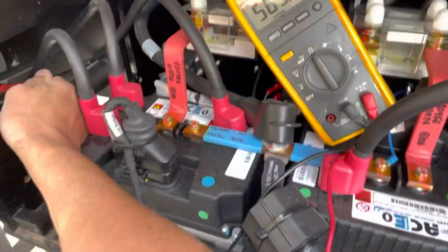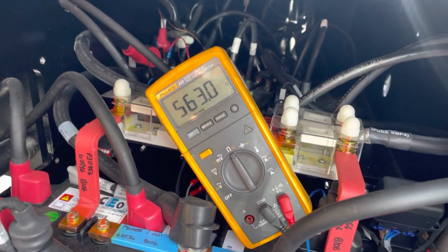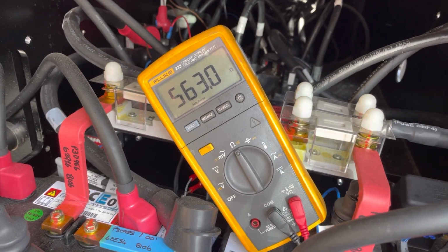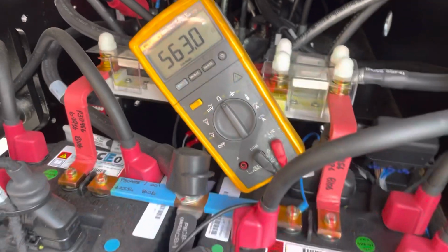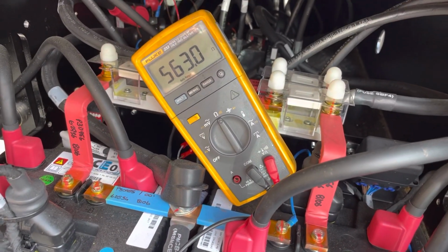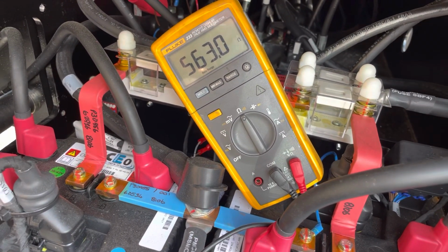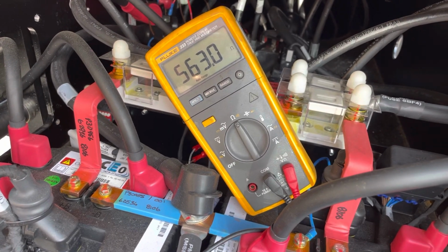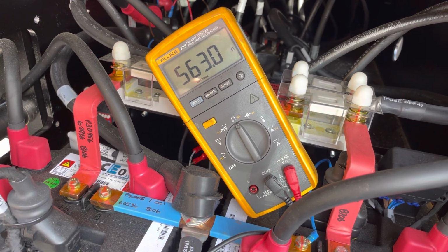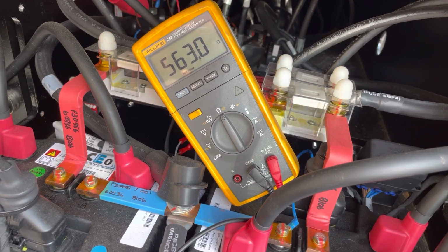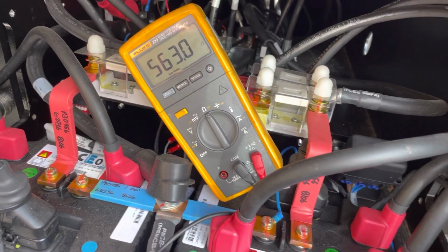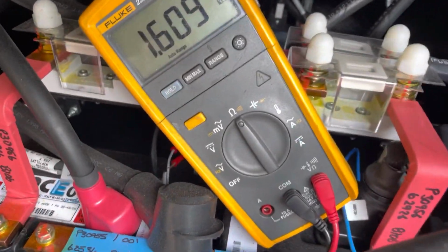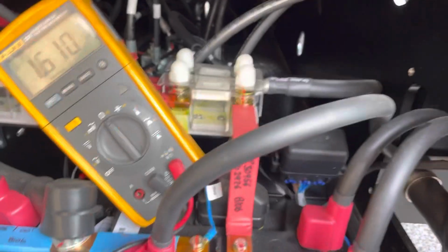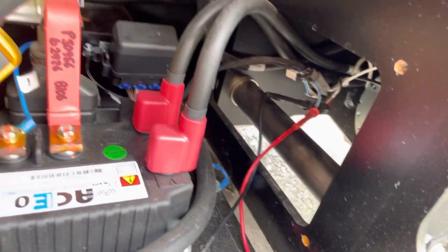So I'm measuring the resistance on the temperature sensor on a slave motor and a slave sensor. So we have around 563 ohms, and that is correct resistance. The outside temperature is about 20 degrees, I would say, today. So roughly that's what we're measuring, 563 ohms. And that's what I would expect to see on the master controller. And on the master side I have 1.6 kilo ohm. Okay, so 1600 ohms, and measuring the temperature on that.